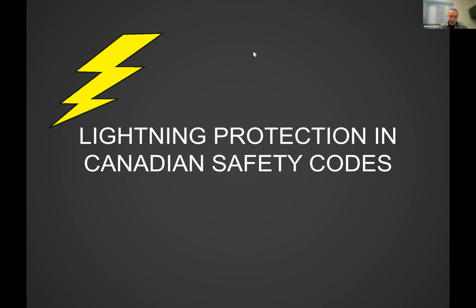You are correct, K Hood. Theft of grounding conductors is a concern. Where theft of grounding conductors is a concern, we will try and use a concealed system. We'll try and put the stuff inside the building. Failing that, we will put our conductor inside a rigid conduit. We are allowed to use metallic conduit. We just have to be sure to bond it to the lightning protection conductor that goes through it, top and bottom, to prevent any inductive choking effects.